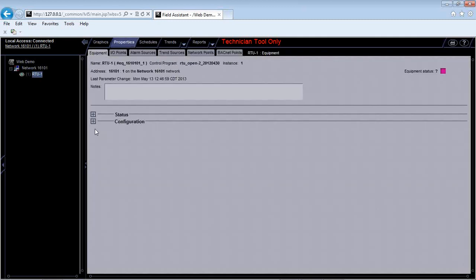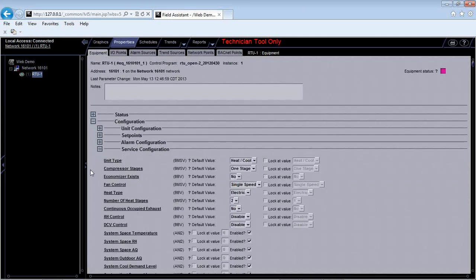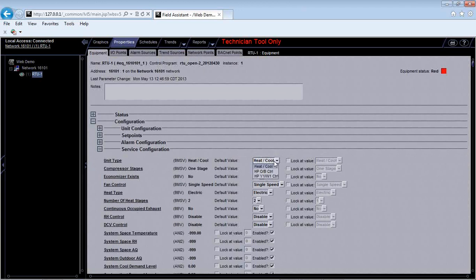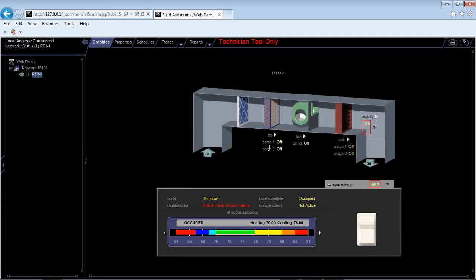If I go into Properties, Configuration, Service Configuration, now this is where I tell the unit I have heating and cooling or I have heat pump control. That would be my first one. I can tell it how many stages of DX it has. So let's say I want to switch to 2 stages. If I switch that and hit OK, it's going to show up as 2 stages. If I go back to my graphic, now it's going to auto-generate the new graphic where I have 2 stages of compression. Okay. All of the logic and graphics are already programmed on the unit. You just need to configure the unit so it knows what it has.